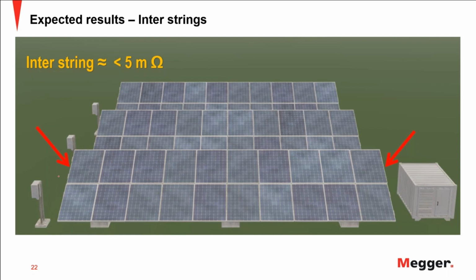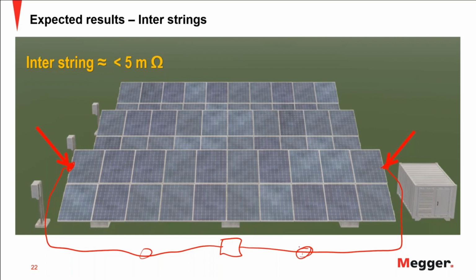And so basically you want to connect one of your leads here and the other set of leads here. So in the end, you're going to have your instrument somewhere in the middle and a set of long leads. This also tells you that the two-wire method is not going to help you, because the resistance of these conductors is going to be much higher than the resistance that you want to measure. So you need to use a set of reels to be able to do this measurement.